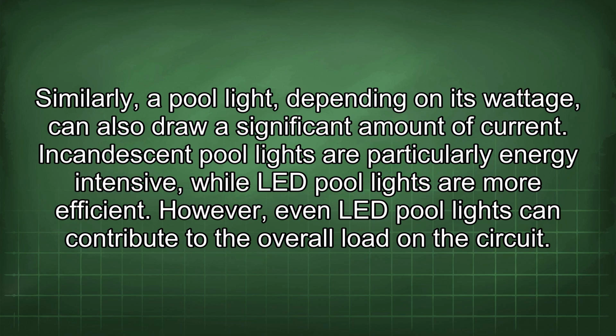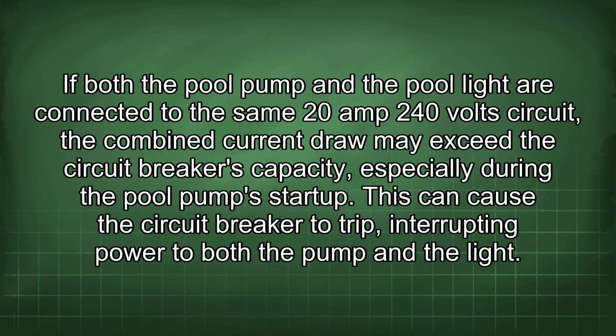Similarly, a pool light, depending on its wattage, can also draw a significant amount of current. Incandescent pool lights are particularly energy intensive, while LED pool lights are more efficient. However, even LED pool lights can contribute to the overall load on the circuit. If both the pool pump and the pool light are connected to the same 20-amp 240-volt circuit, the combined current draw may exceed the circuit breaker's capacity, especially during the pool pump startup. This can cause the circuit breaker to trip, interrupting power to both the pump and the light.